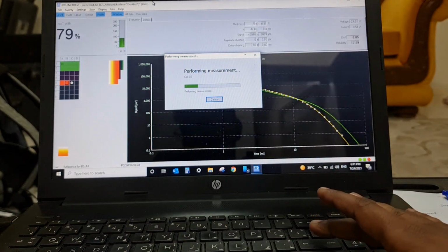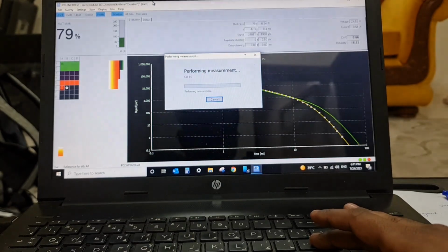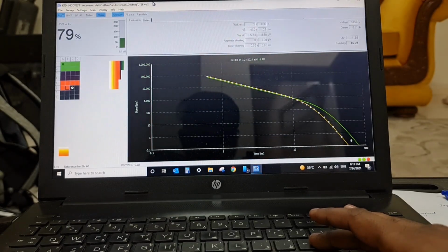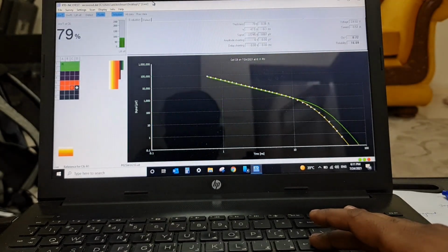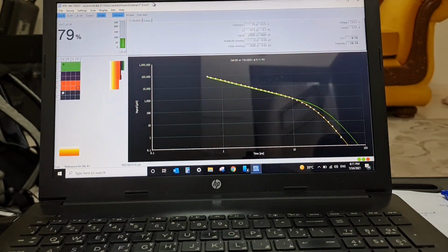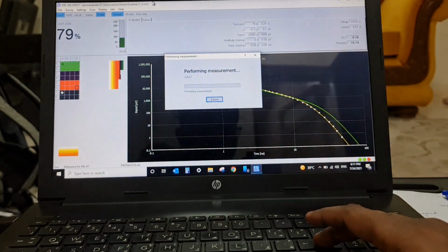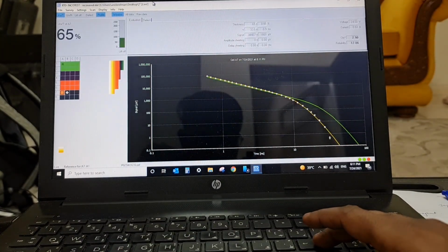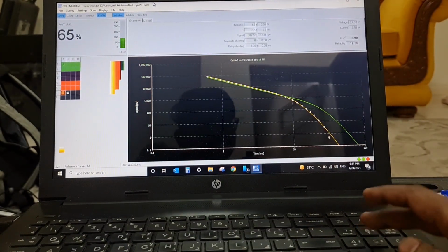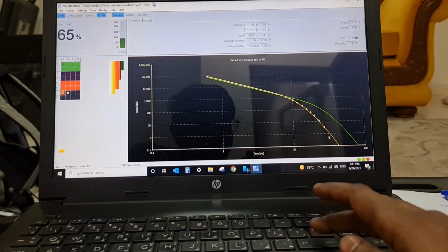Actually EncoTest is very consistent and repeatable. Even if we do 3 or 4 times at the same point, we will get the same reading. In the meanwhile, if we observe the display on the right side, we are able to see the steps, and on the downside we are also getting a cross section. And the third step is completed, and we are moving to the fourth step.